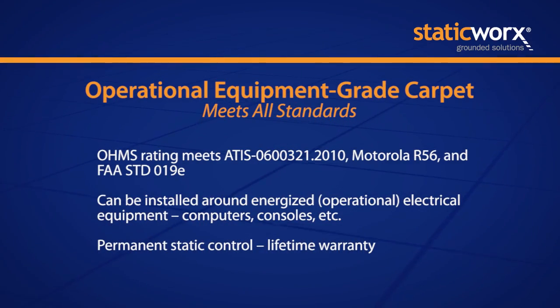And that brings us to the third type of carpet, what we're calling operational equipment grade carpet. And what this carpet is made to do is to drain static electricity, but to do it at a controlled rate and to do it with an ohms rating that allows you the possibility of touching voltage and the floor not being so conductive that it's going to become a harmful path to ground.